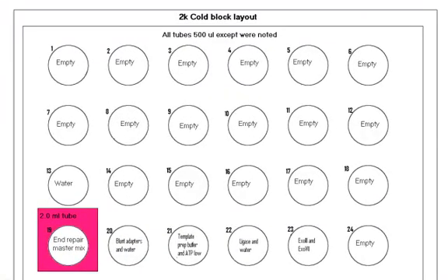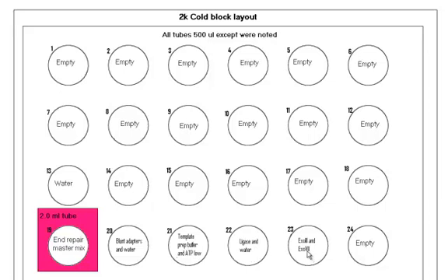Let's look at our cold block. If we tell the method we're going to make the master mixes ourselves, it's going to pop a window open that's going to tell us the volumes to mix together. This is where you're going to place them in the cold block tube. In location 19, we'll have the end repair master mix. In location 20, the blunt adapter and water. 21, template prep buffer and ATP low. 22, ligase and water. 23 is our EXO master mix. All the other locations will be empty.